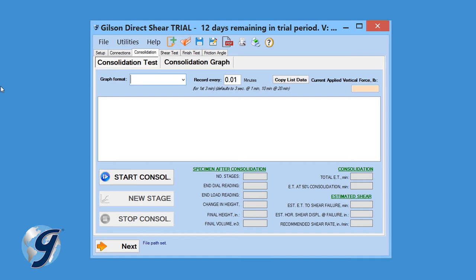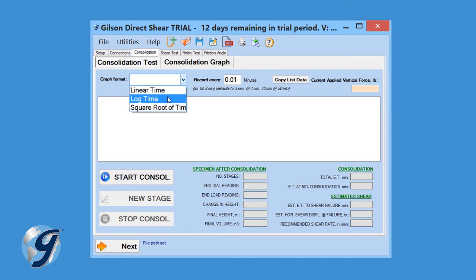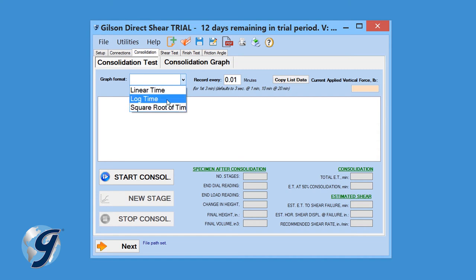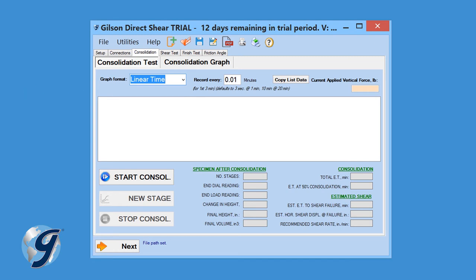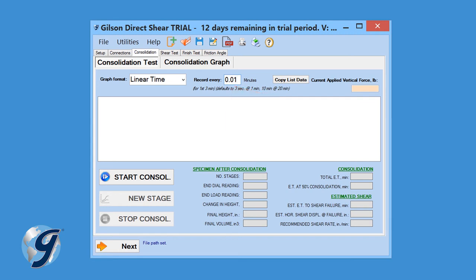In the Consolidation tab, select the graphing format from the drop-down menu. The graph can be displayed in linear time, log time, or the square root of time. The recording frequency defaults to 0.01 minutes for the first 3 minutes of testing, but can be adjusted by entering a different value in the recording frequency field. Then click Start Consolidation.